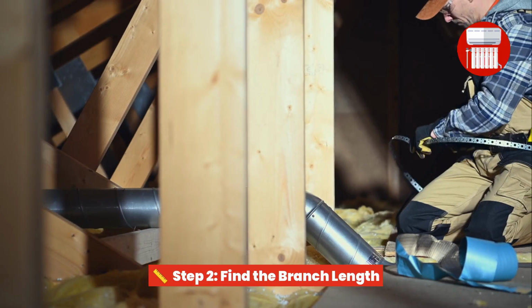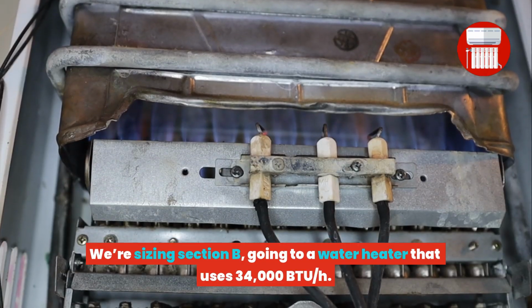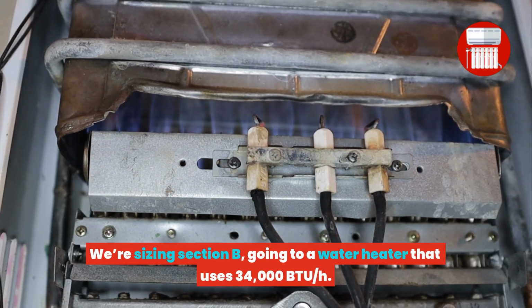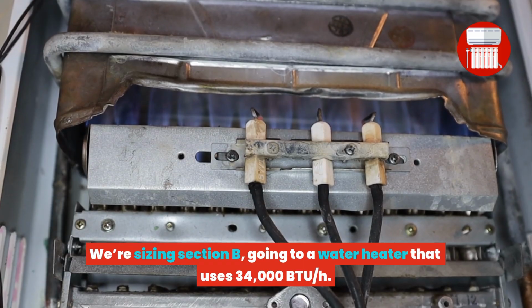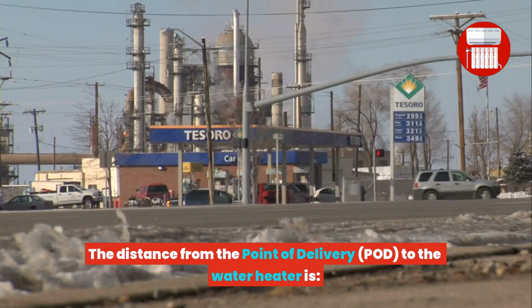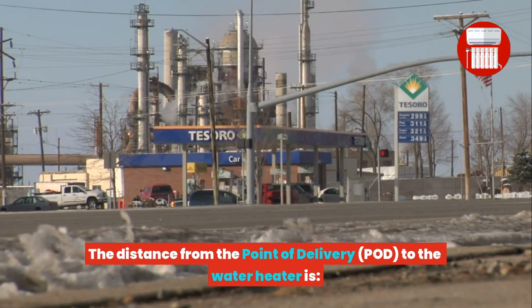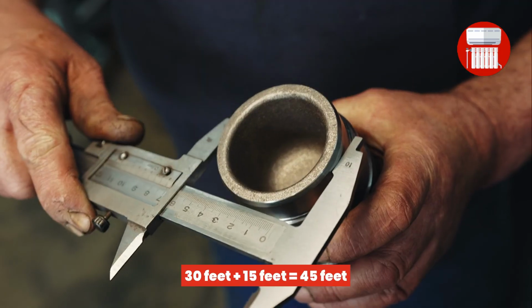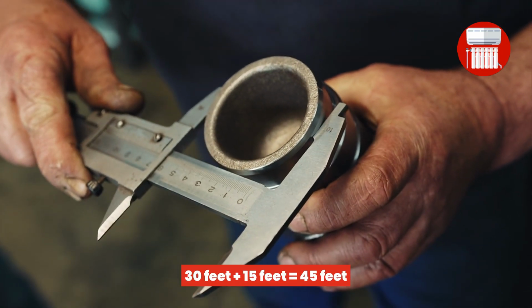Step 2: Find the branch length. We're sizing section B, going to a water heater that uses 34,000 BTU per hour. The distance from the point of delivery (POD) to the water heater is 30 feet plus 15 feet, which equals 45 feet.